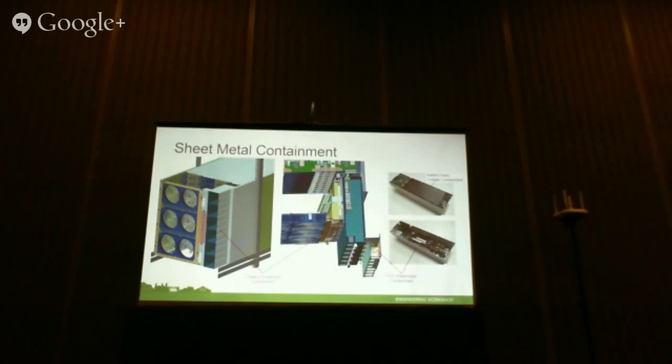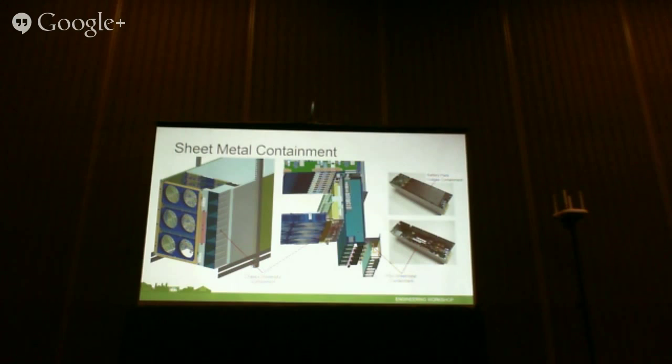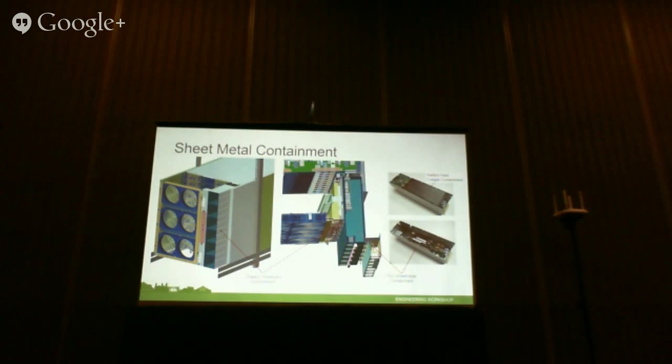Question is, do we have power down on locks? And that is not in our system today. The purpose of the battery is to bridge from one source to another source. It can be from AC grid to a generator, per se. And there is redundancy built into that also. So we have no single point of failure that can take down the server.